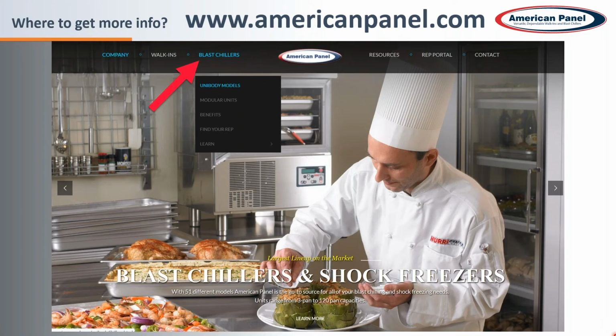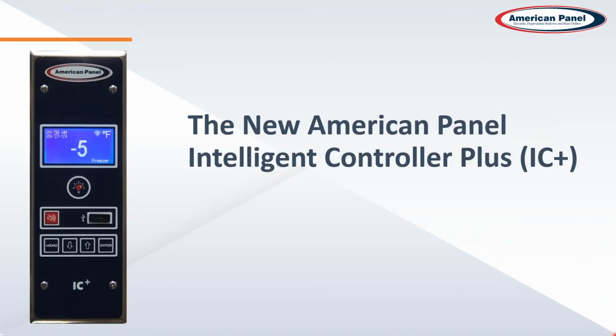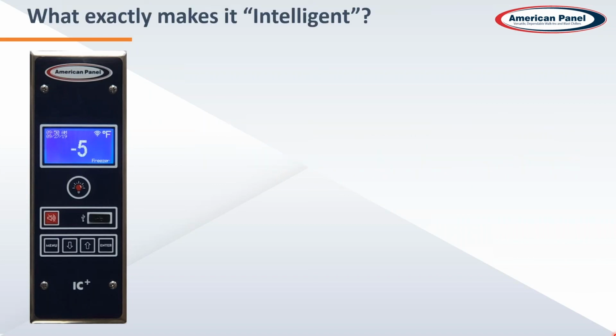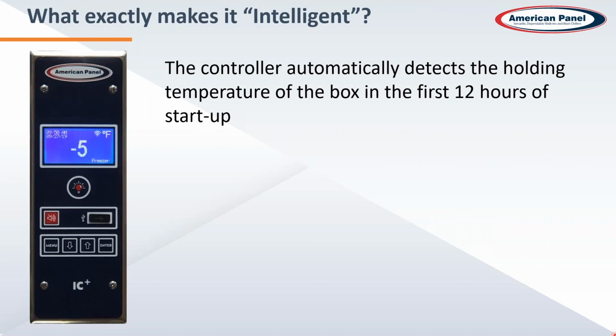Next, we are going to talk about the new American Panel Intelligent Plus controller. So from here on out, we're going to call it IC Plus because that's a lot easier to say. So first of all, what exactly makes it intelligent? It's a very important question. The controller will automatically detect the holding temperature of the box in the first 12 hours of startup. If any of you are familiar with our previous System 100 and System 200 controls, those had to be set up so that you basically told the unit, is this going to be a cooler? Is this going to be a freezer? For a couple of different reasons.